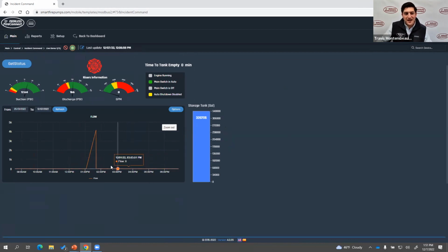It's not live right now. There was a flow blip on the last flow test here, so up to 4,100 GPM for a brief period of time, and then they shut the pump off. So we were able to capture this live while looking at your storage tank. In the event of an incident, you would go to this page, you would see your discharge pressure and your suction pressure, you'd see the flow of the pump here, and the output on the graph.